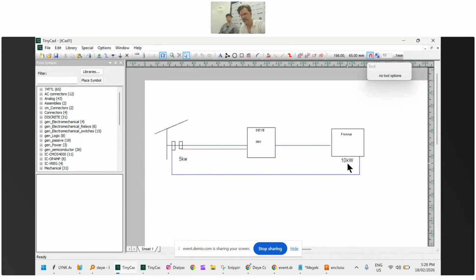In which case, what the Fronius would do is that it would export limit itself to 5 because it can't see the meter, so it's just only going to put out 5. Whereas when the meter is there, it will put out more than 5 if it can see that the meter is 5 or below. The issue with that, obviously, is that when you're in off-grid mode, you're then limited to 5 kilowatts, even though you've got a 10 kilowatt Fronius inverter. And it also makes things a little bit more complicated with the 2 meters with the Deye, with the export control as well. Hopefully that answers your question.